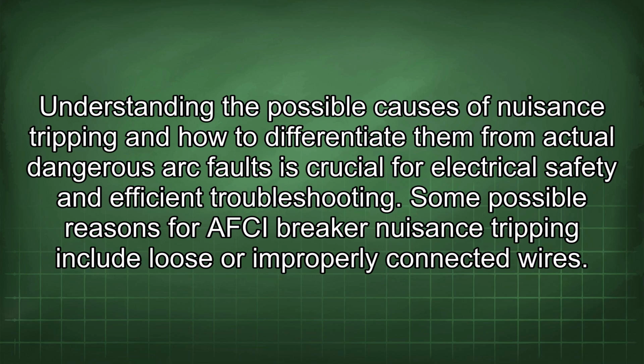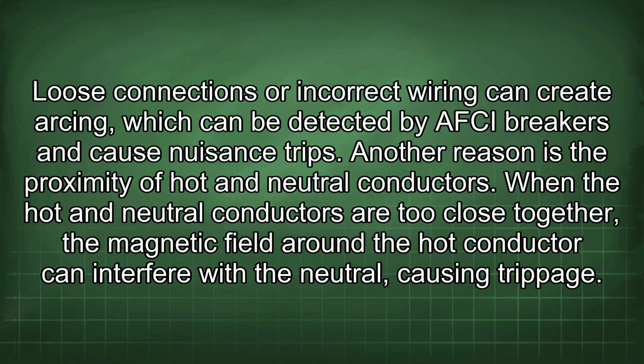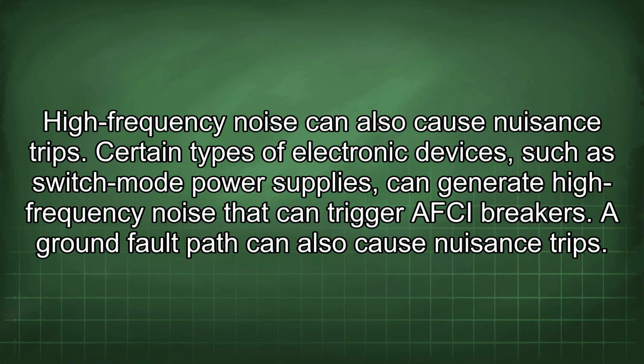Some possible reasons for AFCI breaker nuisance tripping include loose or improperly connected wires. Loose connections or incorrect wiring can create arcing, which can be detected by AFCI breakers and cause nuisance trips. Another reason is the proximity of hot and neutral conductors. When the hot and neutral conductors are too close together, the magnetic field around the hot conductor can interfere with the neutral, causing trippage. High-frequency noise can also cause nuisance trips. Certain types of electronic devices, such as switch-mode power supplies, can generate high-frequency noise that can trigger AFCI breakers.